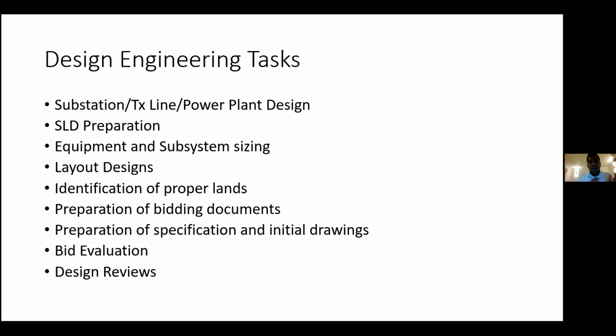There are a lot of previous designs that they have done. Using those designs, they prepare single line diagrams, and they design what is the requirement of equipment and subsystems, and they define the sizing of those equipment and subsystems - equipment like transformers, circuit breakers, current transformers, voltage transformers, disconnectors, bus bars. So they design these systems and define the parameters of such equipment.